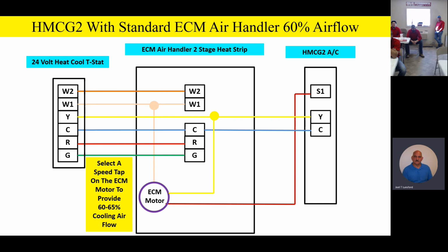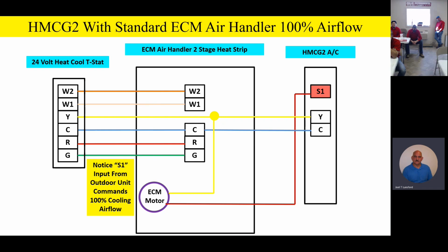So what happens is, when the unit's in the cooling mode of operation and it calls for cooling, it's going to be 60% airflow. However, when the outdoor unit says, hey, I'm at 90% capacity, or actually it's about 70% capacity, it'll generate that S1 signal and drive the indoor unit to 100% airflow. So from about 70 to 100% capacity, you're going to have 100% airflow. The whole theme here with the outdoor unit, the straight cooling product, is that we're letting the outdoor unit directly affect the airflow inside without the use of a relay. Any questions on that?